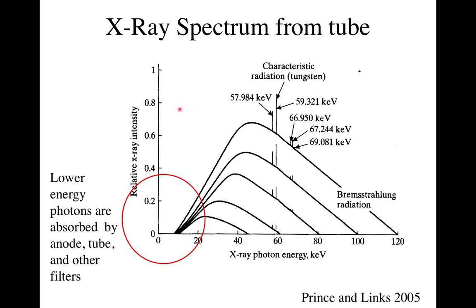Those low-energy photons that are filtered out would never make it through the patient — zero probability of getting out the back. All they would do is deposit energy (dose) in the patient without improving your image. If we turn the dial down to 100 keV peak, we get a different spectrum of X-rays. So you can change the spectrum on your system.